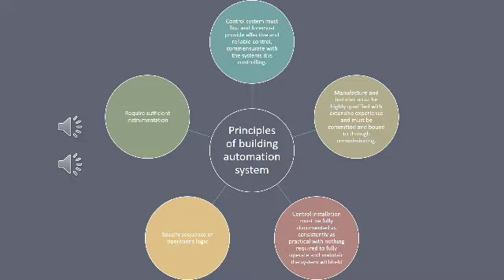An example of a distributed control system in the building is mostly a computer network of electronic devices that has been designed to monitor and control the mechanical, security, fire and flood safety, lighting, especially emergency lighting, HVAC and humidity control and ventilation systems that are installed in the building to keep the occupants comfortable. The system has a BAS core that functions to keep the building climate within a specific range and provide light to rooms based on the occupancy schedule and mostly based on natural lighting.